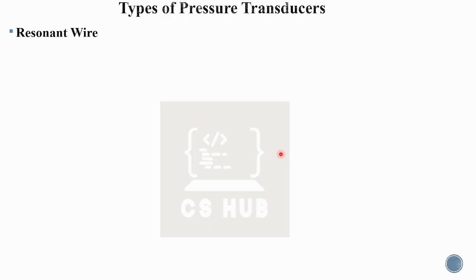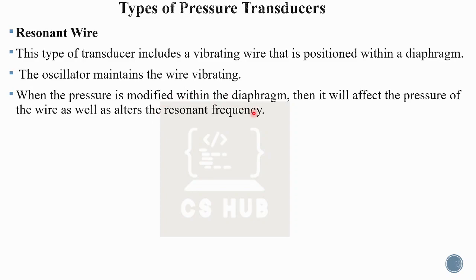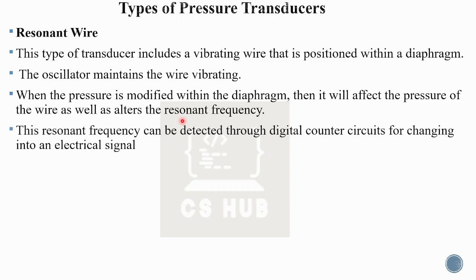The resonant wire transducer uses a vibrating wire placed within a diaphragm. An oscillator maintains the wire at resonance. When the pressure changes, it affects the tension of the wire and alters the resonant frequency. This resonant frequency can be detected through a digital counter circuit and converted into an electrical signal. Normally the wire vibrates at one particular frequency, and when pressure changes, the resonant frequency changes, which is then measured and converted to an electrical output.